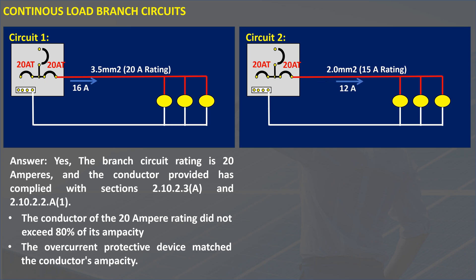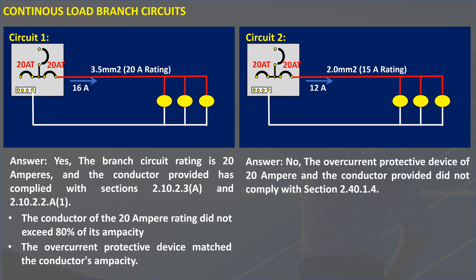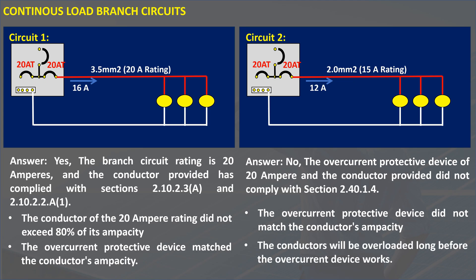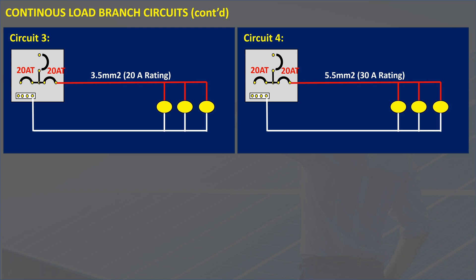How about circuit 2? A 12 amperes continuous load is connected to a branch circuit rated at 20 amperes with a conductor rated at 15 amperes. Is this circuit compliant with the code? No. The overcurrent protective device of 20 amperes and the conductor provided did not comply with Section 2.40.1.4. The overcurrent protective device did not match the conductor's ampacity. The conductors will be overloaded long before the overcurrent device works.